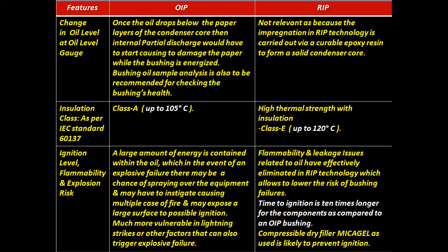For RIP bushings, flammability and leakage issues related to oil have effectively been eliminated in RIP technology, which lowers the risk of bushing failures. Time to ignition is 10 times longer for these components as compared to OIP bushings. The compressible dry filler, MICAGEL, as used, is likely to prevent ignition.